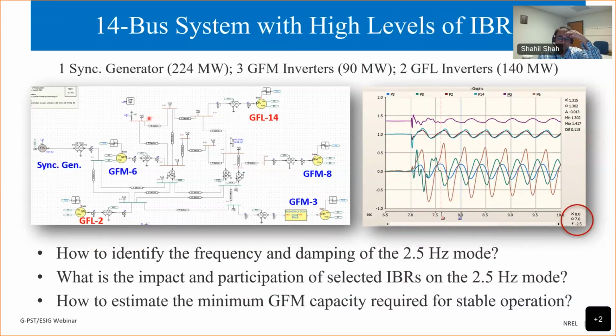And during some contingency or fault event, we see some oscillations in this system, 2.5 hertz oscillations. The question is how we can use the impedance scan software tool that I just described to understand the stability: how to identify the frequency and damping of modes which we are not aware of, how to understand the impact and participation of different IBRs on that mode, and also whether we can estimate the amount of grid forming inverter capacity that is required for stable operation using this tool. So let's first perform the scan.